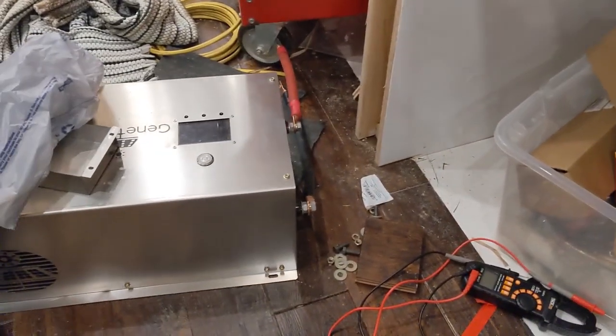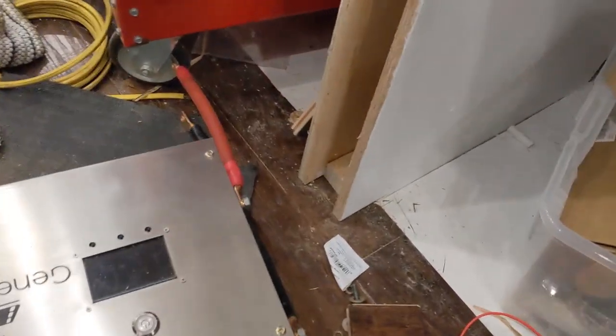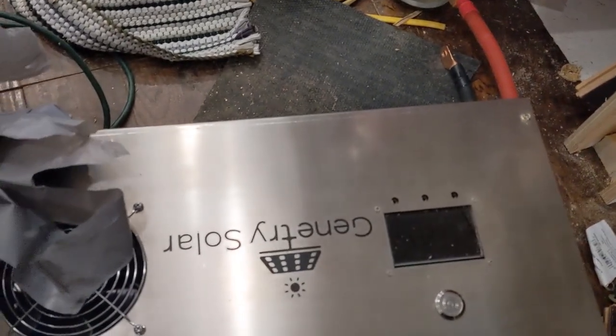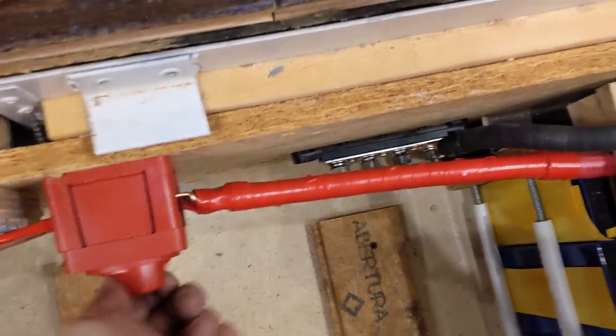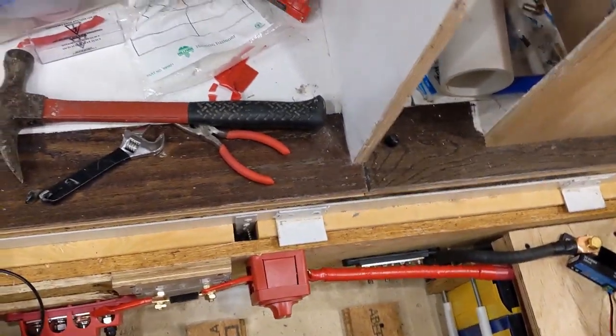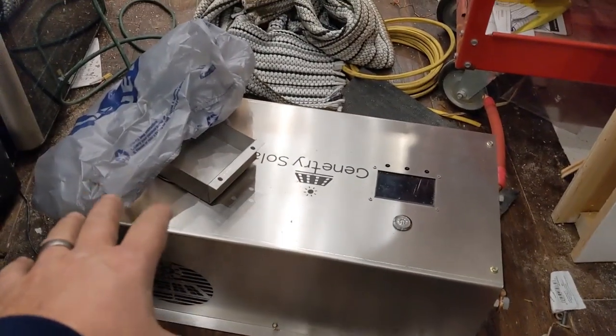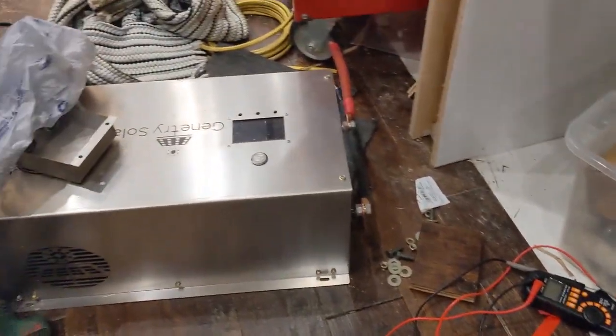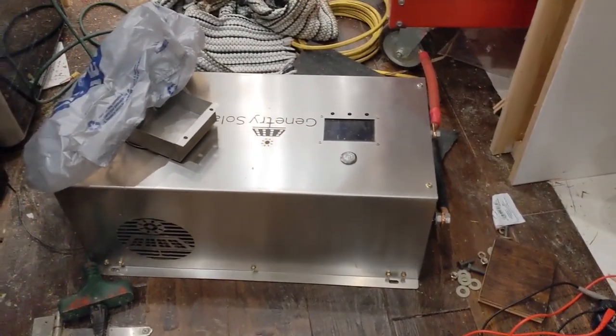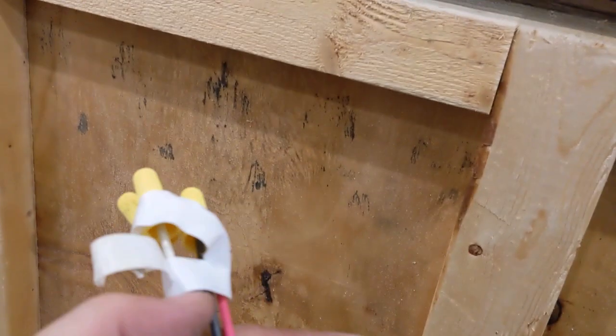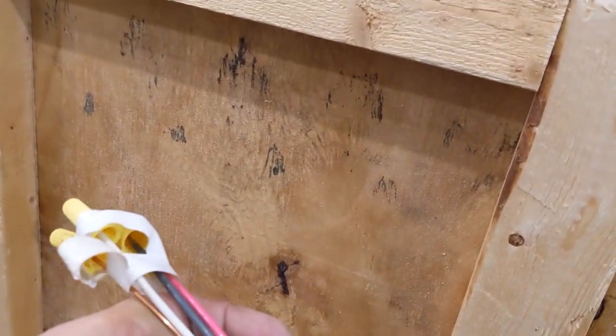Alright, so now that I got the correct voltages where I was checking them, I'm actually going to get this Genetry solar inverter connected. First thing I'm going to do is shut off this battery shutoff. And after that, I'm going to wire in AC wiring on one side and DC on the other. And I'll leave the AC breaker off. I'm actually going to do a 120 volt AC. I had intended to do 240, but based on the way the inverter works, that's not gonna function. So this live connection here is going to get curled up and reserved for potential future use.